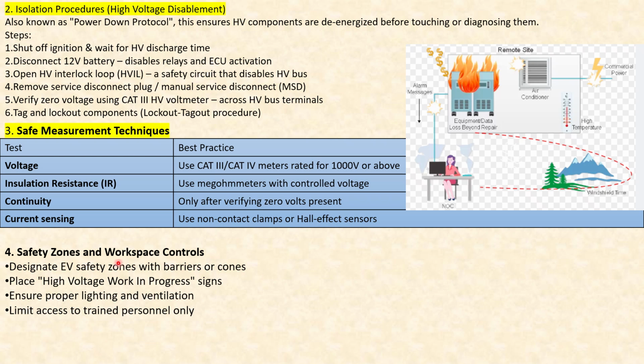Okay, so talking about the safety zones and workplace controls, designate EV safety zones with barriers or cones. EV safety zones must be clearly barricaded with the help of barriers and cones, and boards like high voltage work in progress signs should be put up. Now, ensure proper lighting and ventilation, and limit access to trained personnel only. All right, because it's a very dangerous zone, only trained personnel should enter it, and it must be mandated.